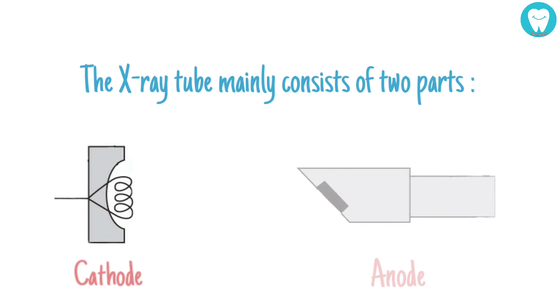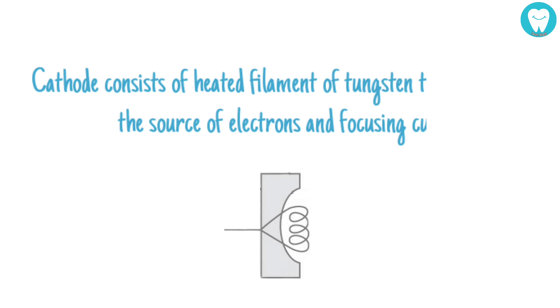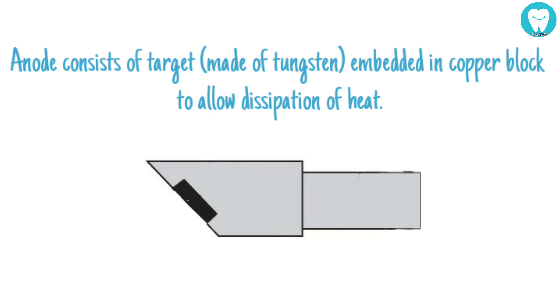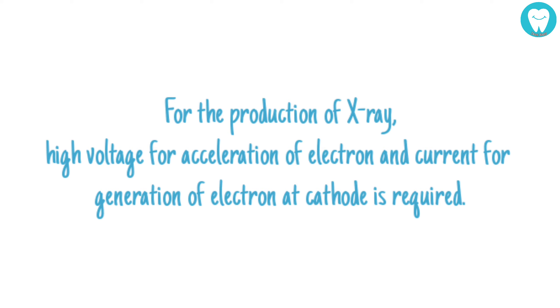The X-ray tube mainly consists of two parts: cathode and anode. The cathode consists of a heated tungsten filament that provides the source of electrons and a focusing cup. The anode consists of a tungsten target embedded in a copper block to allow dissipation of heat. For the production of X-rays, high voltage for acceleration of electrons and current for generation of electrons at the cathode is required.